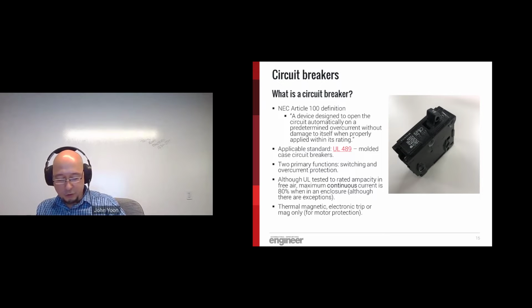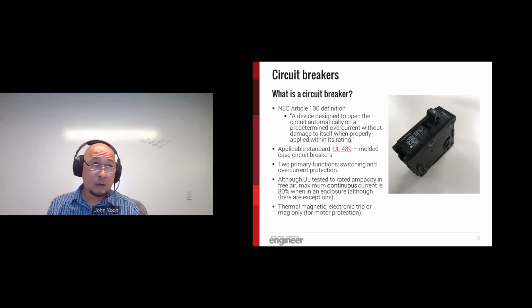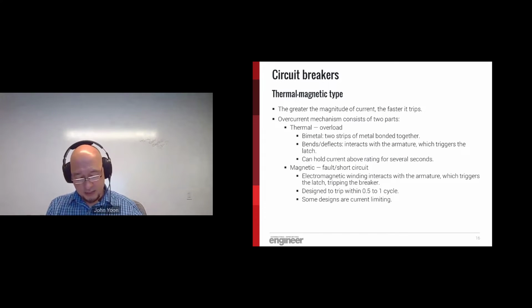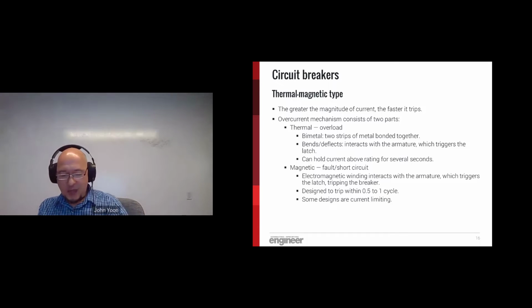When they're installed within an enclosure, unless they are specifically rated for 100% duty, they must be derated to 80% when subjected to continuous current. Continuous currents are defined in the NEC for any load that is sustained for 3 hours or greater. Okay, let's move on to the next slide and talk a bit more about this.